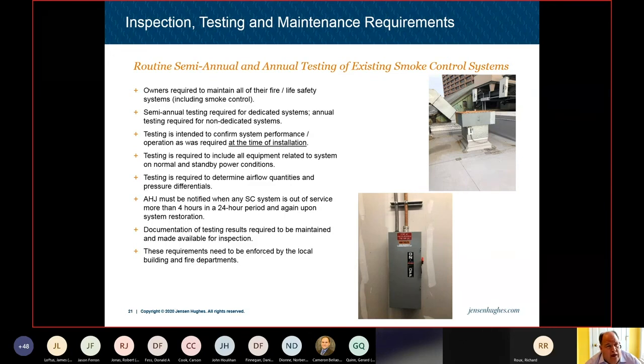Now, some of it is because there's a challenge. This smoke control system, it's not just one system. It's a combination and integration of a bunch of systems. So unlike if someone wants to service their fire alarm system, there's a lot of fire alarm system service companies out there. If someone wants to service their sprinkler systems, there's sprinkler service companies out there. But there's no such thing as a smoke control service company, because really, to do that properly, it's a bunch of service companies that need to get pulled together to properly maintain that system. Fire alarm being one of the integral pieces to that.